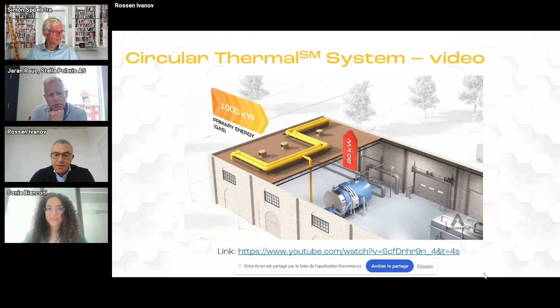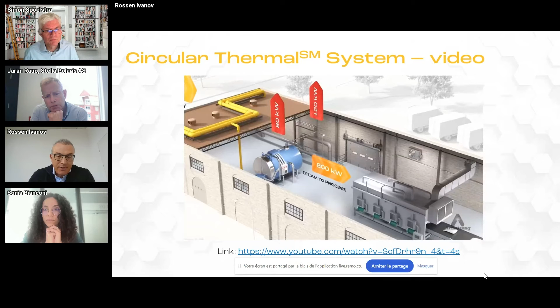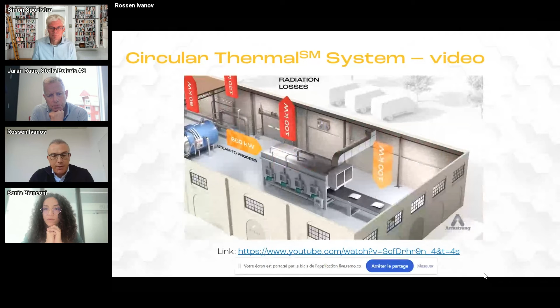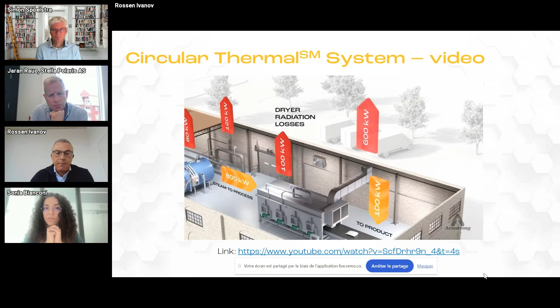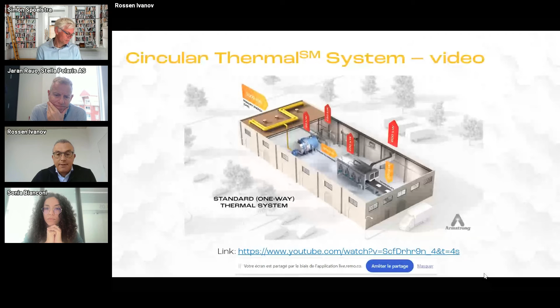Historically, since the Industrial Revolution, we have been using a one-way system. So we are putting energy on one side of the plant, typically natural gas, which is burned in boilers. Part of this energy is lost in the boiler house or in the distribution, condensate return, and flash steam network. Only about 80% of the primary energy ends up in the process, and a very low quantity of that energy goes in the product. Most of the time, energy is wasted in the form of low-grade heat through process stacks.